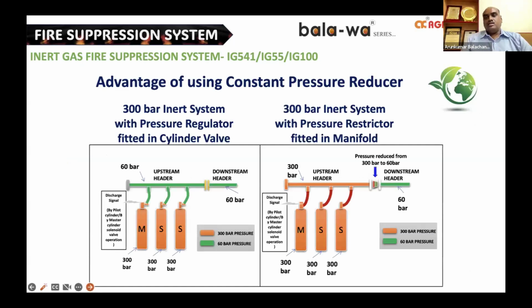I just want to highlight a small system that has been updated in this inert. On your right side, what I'm showing here is an old system which uses a pressure restrictor fitted in the manifold. You can see this here. These are the old type of inert systems which are predominantly used, where a 300 bar inert system in the cylinder, when discharged, will send 300 bar to the upstream manifold, and in the restrictor, it will be stepped down from 300 to 60 bar.